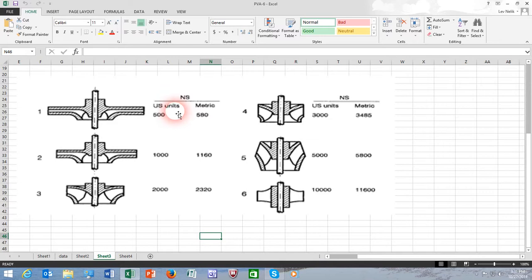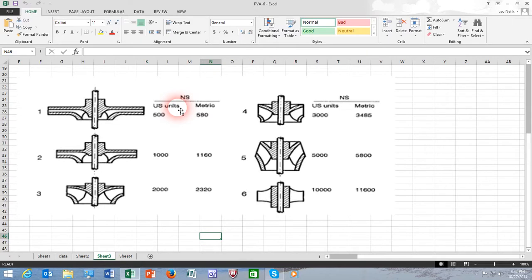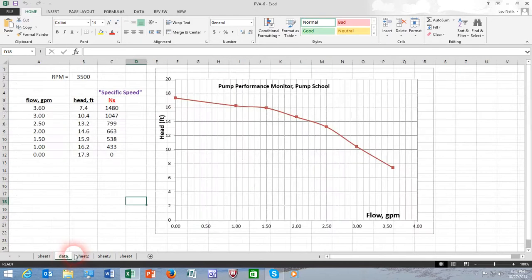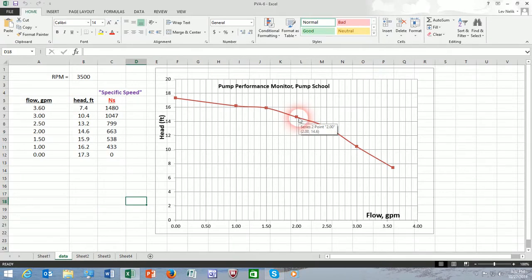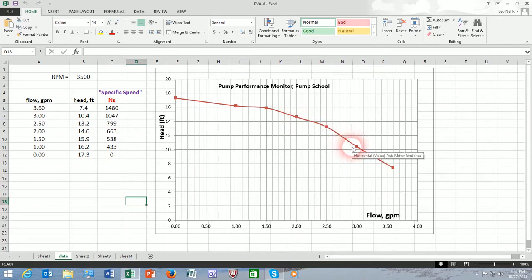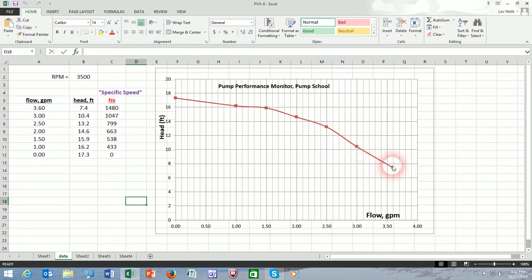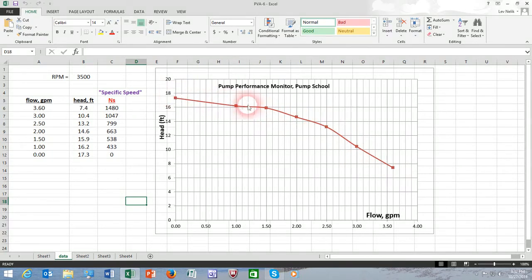So the definition for specific speed must be at a particular point to which everybody would agree. That point happens to be BEP, best efficiency point. At the best efficiency point, we would have nomenclature in compliance with the standards. Which of these points is the BEP point? We don't know. And in this test, that was not part of our charter. All we needed to show is that the specific speed itself varies substantially if it's calculated at different points.